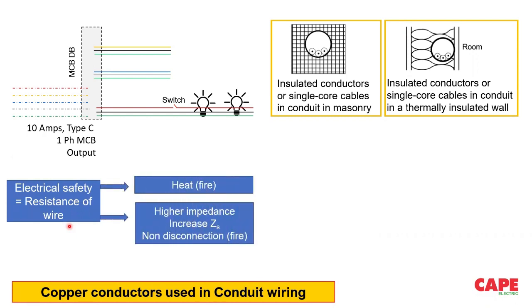So, electrical safety with respect to wire, there are two things. One is what happens before the fire. Next is what happens after the fire. After the fire, insulation is important. The insulation must have very limited smoke density, or in the other sense, the visibility must be much higher for a safe installation.